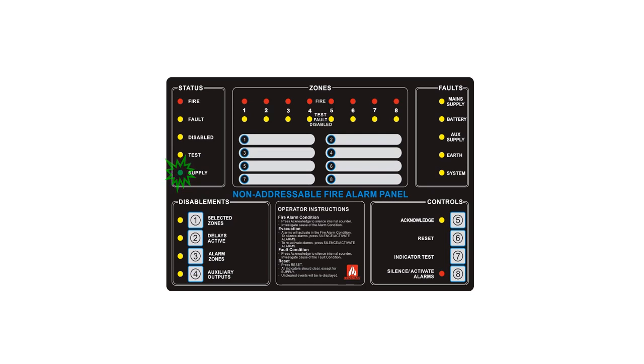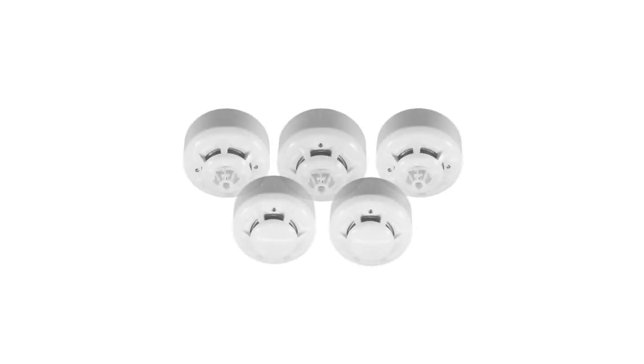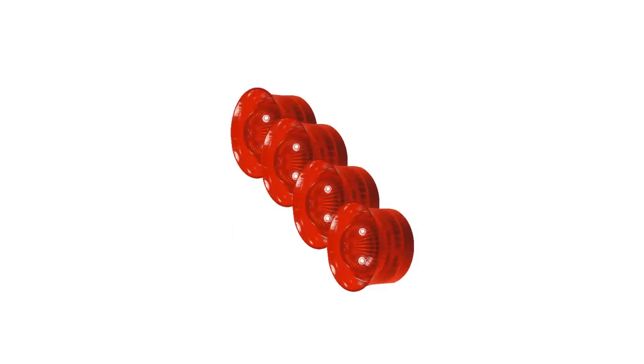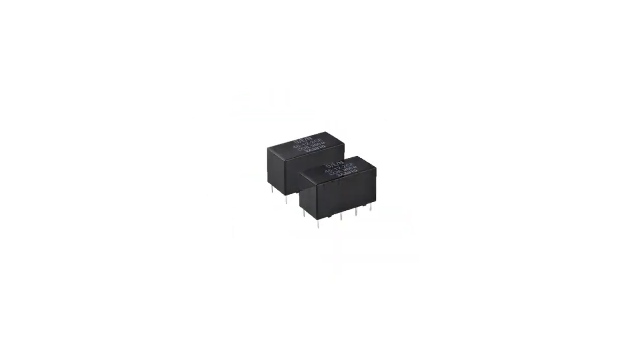Now we have reviewed all the configuration options. And so, with the configuration completed, testing devices and functions will complete the commissioning process. This includes detection devices, audio-visual alarm devices, the output relays on the panel, and any other optional accessories installed as part of the system.